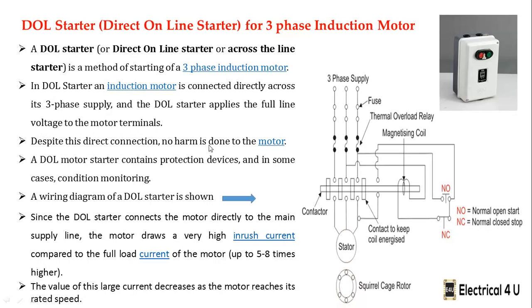Despite this direct connection, no harm is done to the motor. A DOL motor starter contains a protection device and in some cases condition monitoring. A wiring diagram of a DOL starter is shown in this diagram. Since the DOL starter connects the motor directly to the main supply line, the motor draws a very high inrush current compared to the full load current of the motor. That is nothing but 5 to 8 times higher than the rated current. The value of this large current decreases as the motor reaches its rated speed.